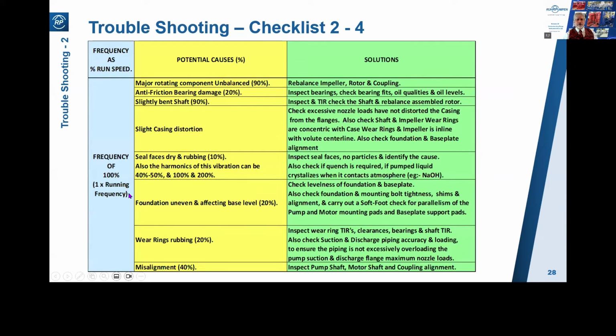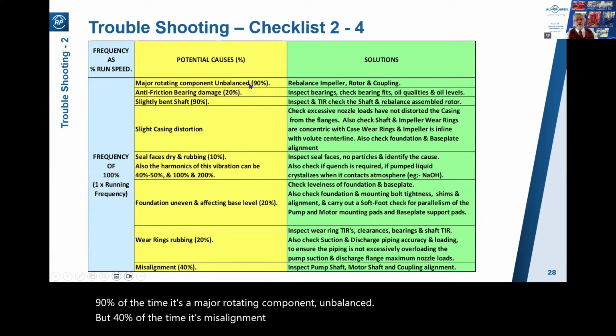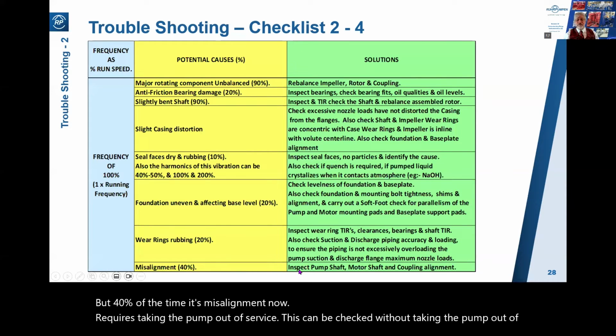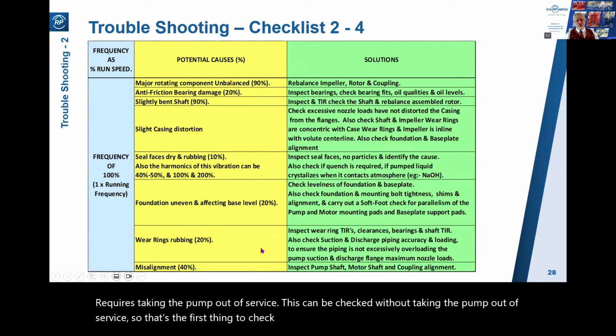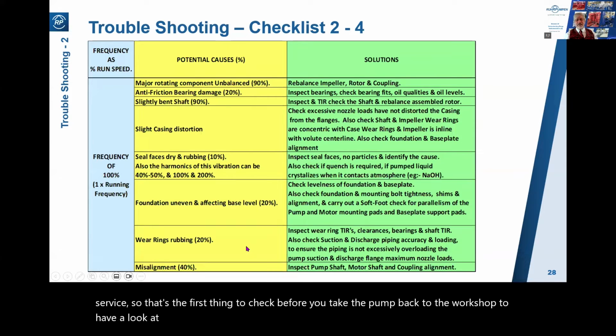And this one is quite interesting in the fourth slide, peaks at running speed. 90% of the time, it's a major rotating component unbalanced. But 40% of the time, it's misalignment. Now, this requires taking the pump out of service. This can be checked without taking the pump out of service. So that's the first thing to check before you take the pump back to the workshop to have a look at it. It's the easy thing to check.